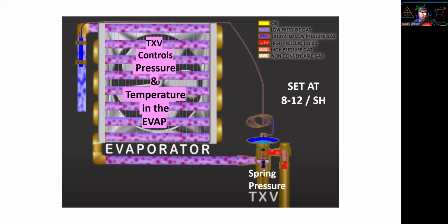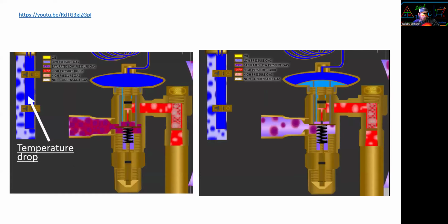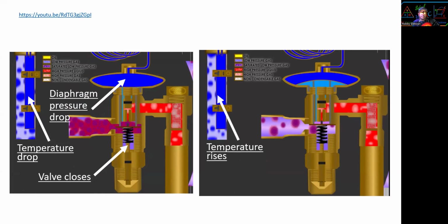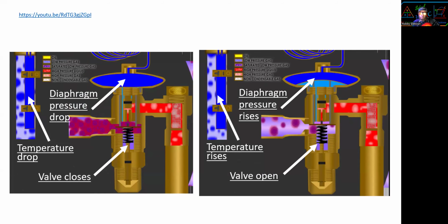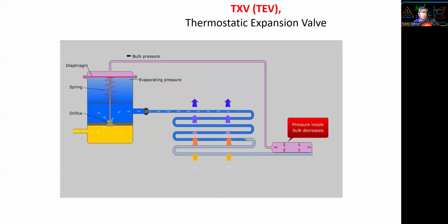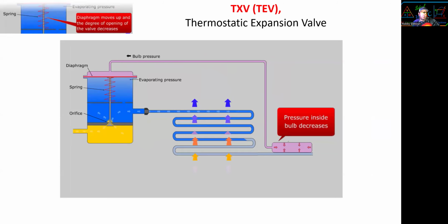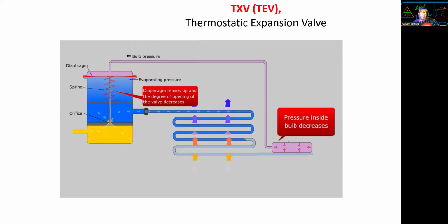All right. Spring is set 8 to 12. I'll cover it more later. As temperature drops, diaphragm pressure will drop. Valve will close. As temperature rises, diaphragm pressure will rise. Valve will open. Okay. Another example. This one from the Danfoss learning I talked about earlier. The pressure inside the bulb decreases. Diaphragm moves up. The degree of opening of the valve decreases. Less freon flow into the evaporator. All right, now let's talk about the standard TXV.